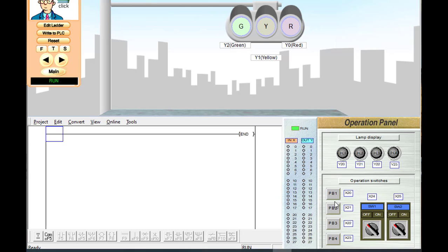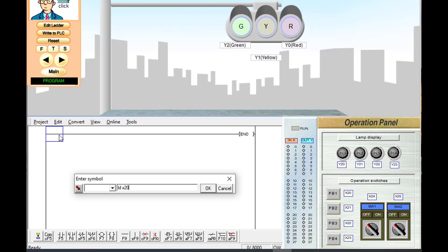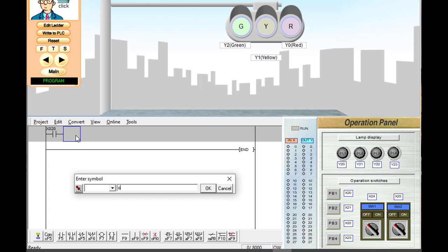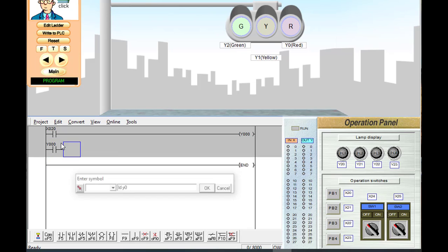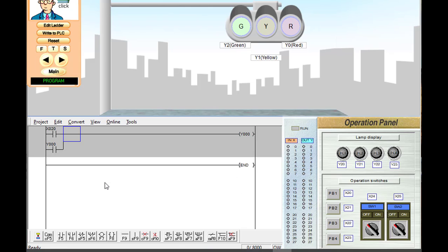The sequence starts when we press push button one, that is X20. When X20 is activated, we have to turn on the red light for 10 seconds. We press the edit ladder button and write the NO contact of X20 — that is push button one. When push button one is pressed, we turn on the red light using output Y0. Since this is a push button, we have to latch the output Y0 so it remains on.